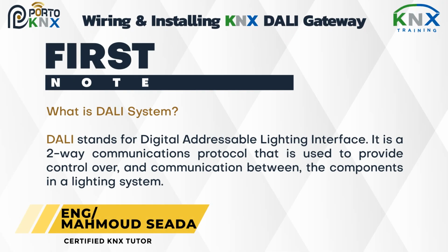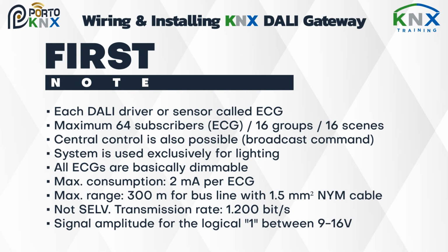First note, what is DALI System? DALI stands for Digital Addressable Lighting Interface. It is a two-way communications protocol that is used to provide control over, and communication between, the components in a lighting system. Each DALI driver or sensor is called ECG, maximum 64 subscribers, ECG, and 16 groups and 16 scenes.